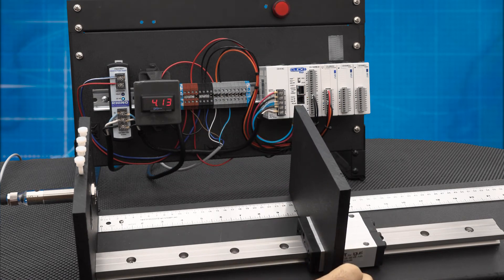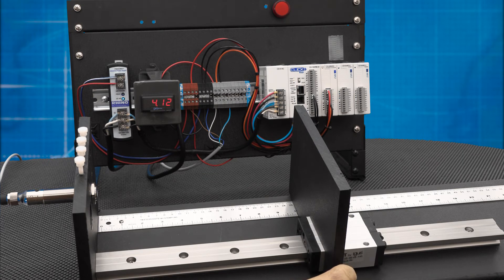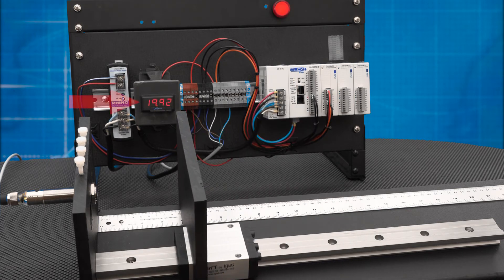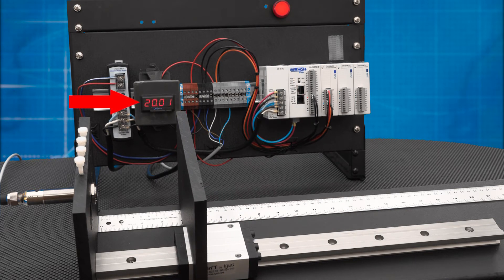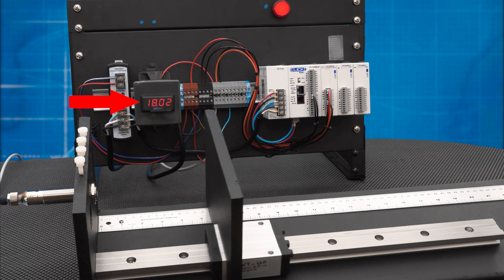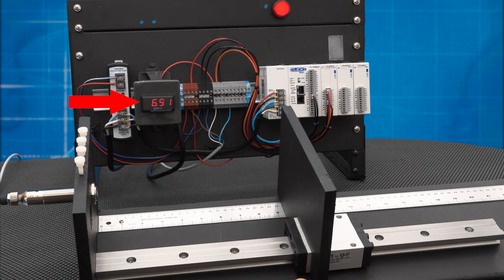The LED will flash faster, then stop. Now our analog display shows 20 when we are at our closest target and 4 when we are at our furthest target, giving us a negative slope.